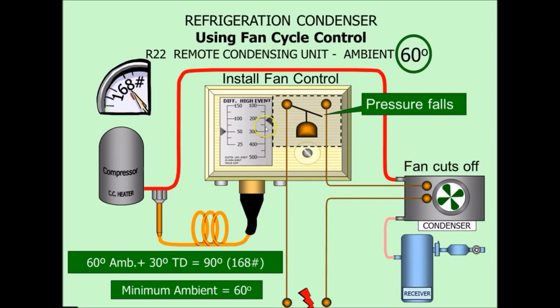So let's take a look at how that works. It's warm during the day, the condenser fan's running, the pressure is above 210 PSIG, and it's humming along without an issue. It gets into the evening, the ambient temperature falls below 60 degrees, and the head pressure starts to drop from 210 to 200 to 180, and on its way down, when it gets to 160, which is the difference between the high event and the differential, 160 PSIG, this switch breaks and shuts the condenser fan off. Because the condenser fan is off, the head pressure begins to rise, and it goes back up from 160, 170, 180, up to 210. The switch comes on, and it maintains that head pressure. So the head pressure is going to stay between 160 and 210 in this example.